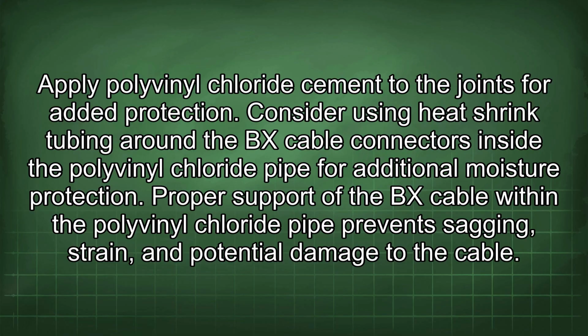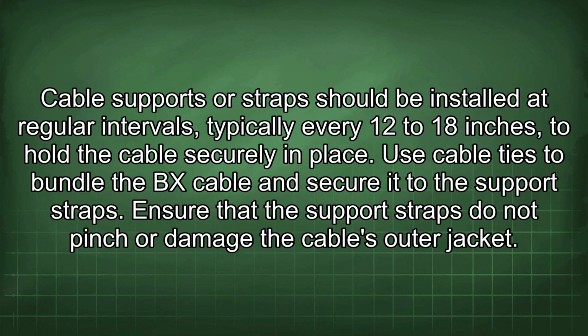Proper support of the BX cable within the polyvinyl chloride pipe prevents sagging, strain, and potential damage to the cable. Cable supports or straps should be installed at regular intervals, typically every 12 to 18 inches, to hold the cable securely in place. Use cable ties to bundle the BX cable and secure it to the support straps. Ensure that the support straps do not pinch or damage the cable's outer jacket.